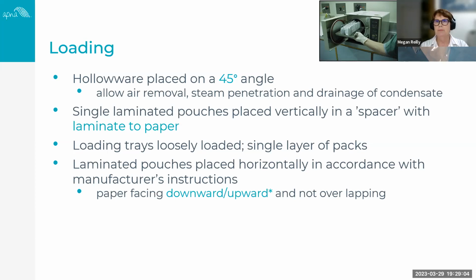In terms of the laminated pouches, the standard, which as I said is very old, actually states that those pouches that are placed horizontally need to be placed with the paper facing downward. But it does depend on the type of sterilizer that you have, because some of the brands, or one of the brands in particular, actually says in the manufacturer's instruction that the paper facing must be upward, but certainly not overlapping. So again, always go back to your equipment manufacturer's instructions.